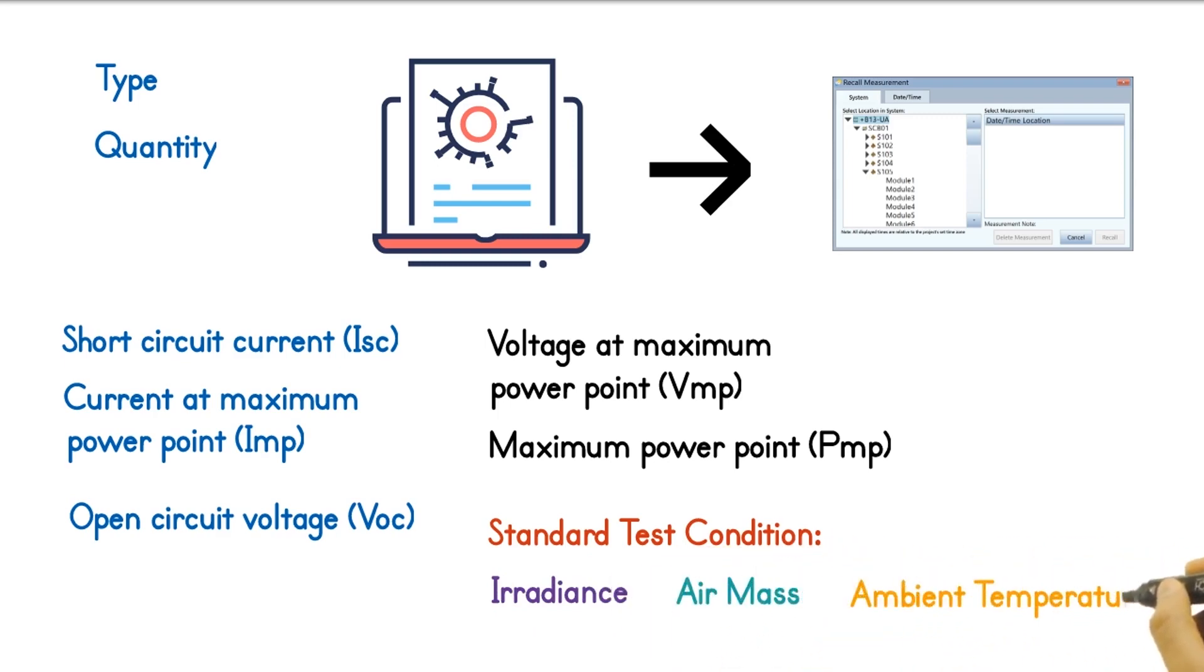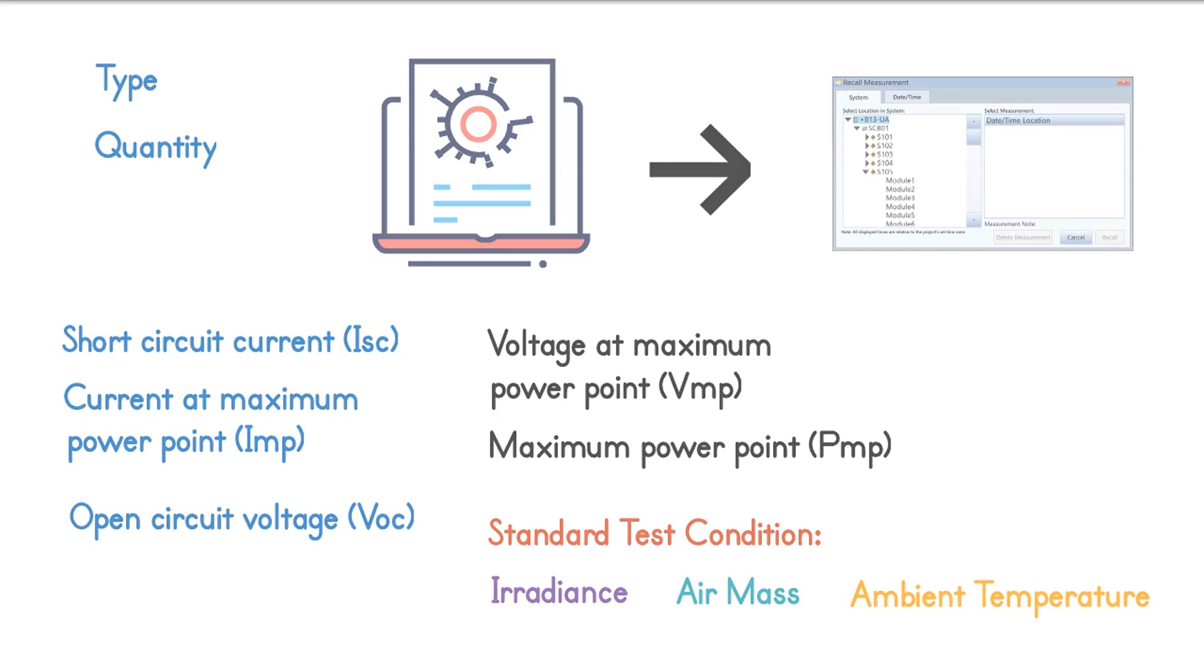But because the conditions in the field where these modules are installed is different from the STC, IV curve tracers use mathematical models to account for the actual conditions in the field and generate a predicted IV curve and maximum power value for the string under test.